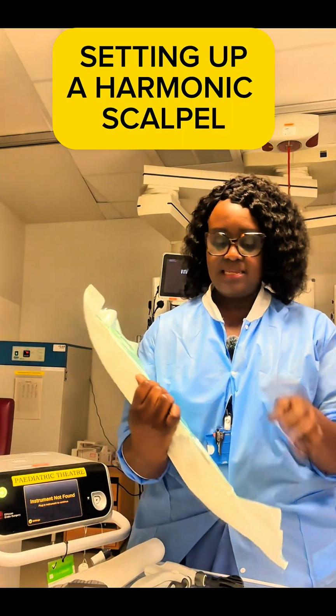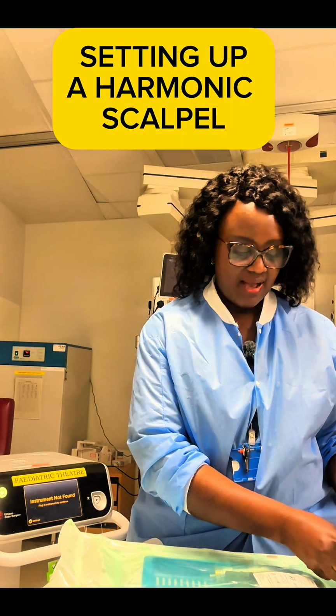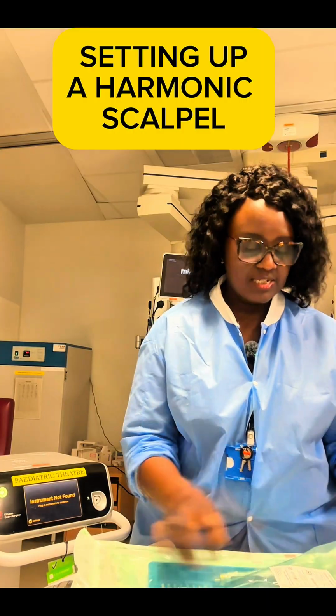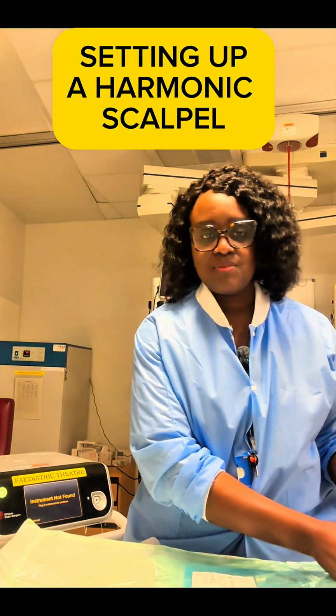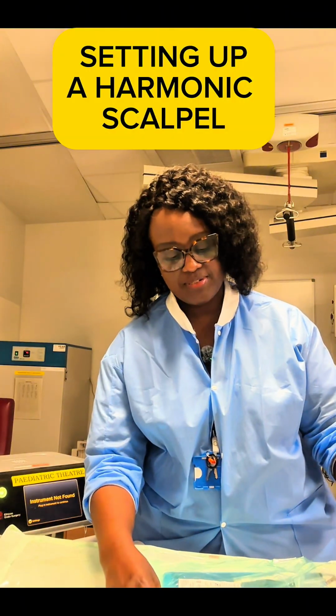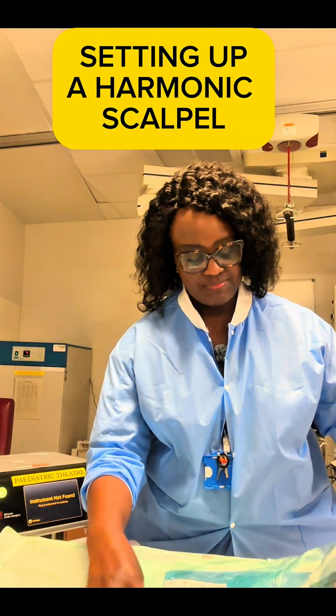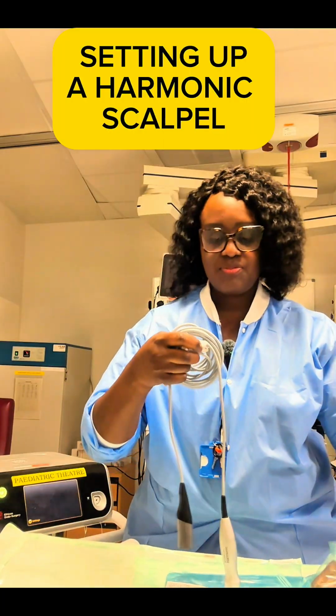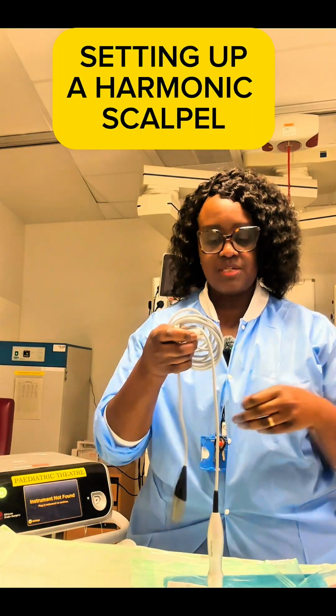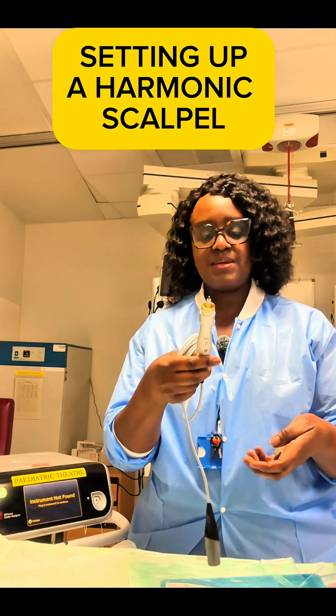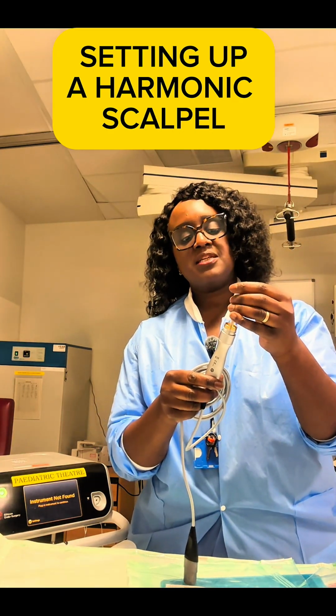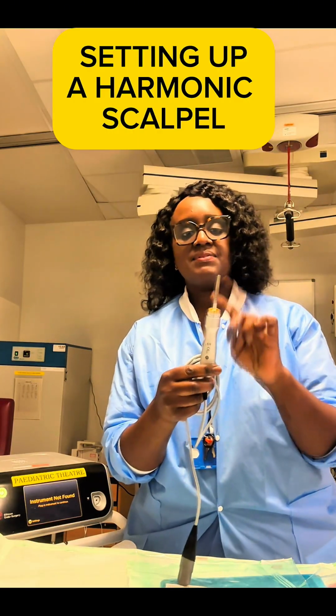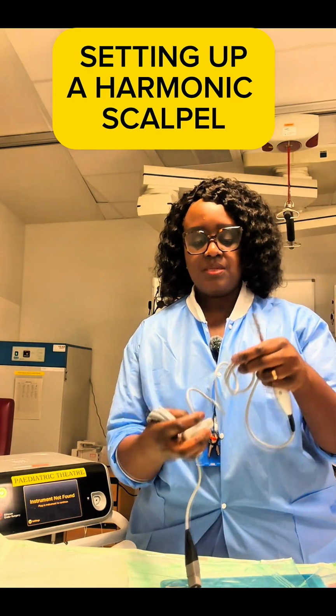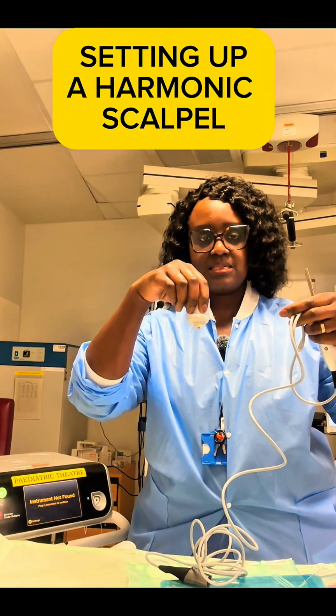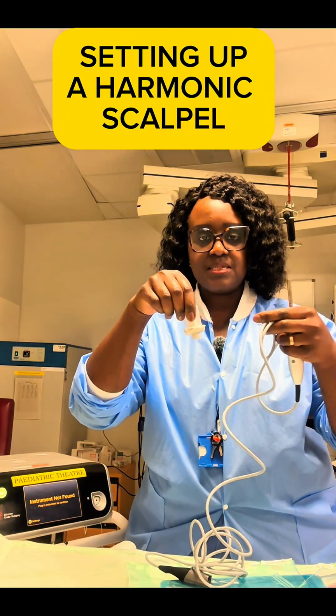This is the handpiece that is reusable, so which means it's always autoclaved to make it sterile. It has 3 parts, which includes this piece here that is meant to cover that bit. Unfortunately, this one is not connected, but anyway, that covers that bit, which you must remove. And then you have the piece that you use to lock the handpiece to the piece of equipment itself.